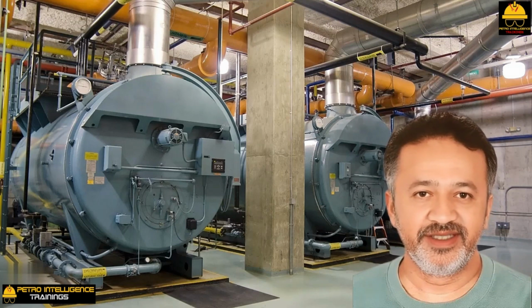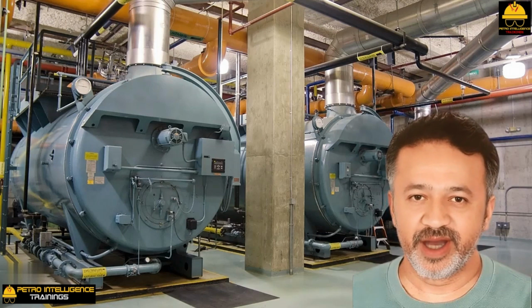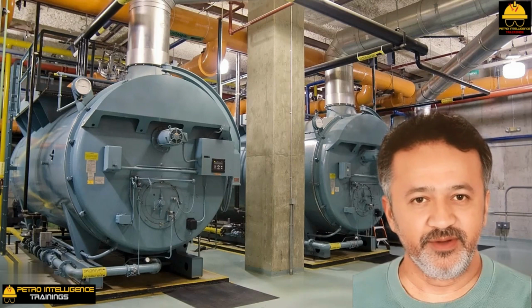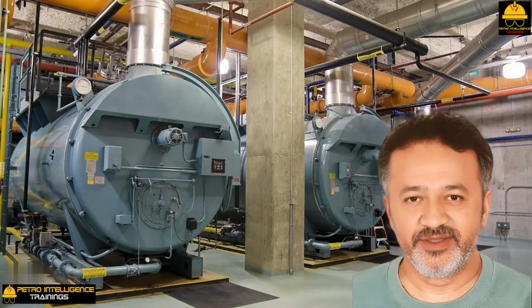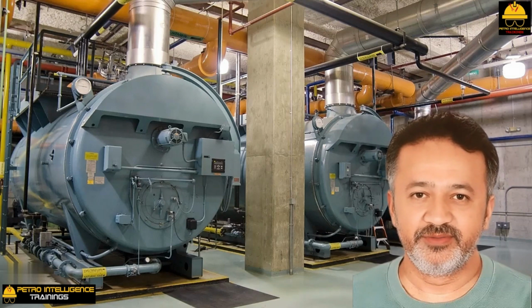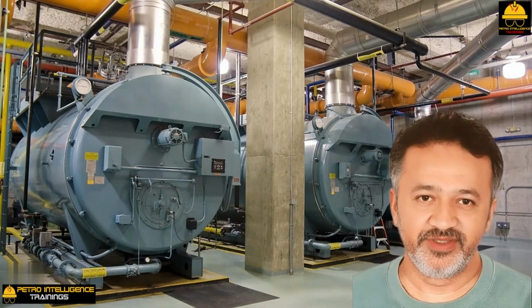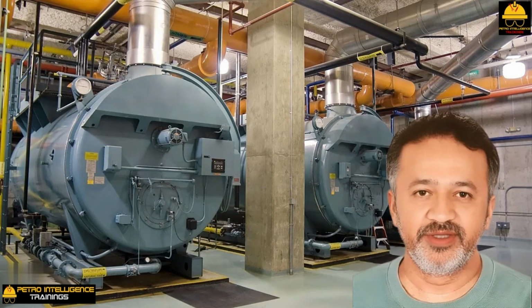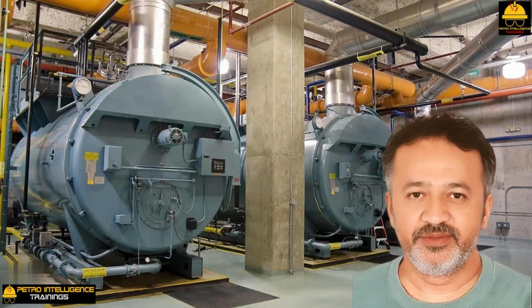Depositing on turbine blades. The deposits eventually get so thick that they break off and unbalance the rotor. Resulting vibrations then cause the turbine to trip off, and stress corrosion of the blades causes sudden failure. Fouling of vacuum system ejector steam nozzles. The TDS content of BFW should be minimized by upstream treating. In former days, hot lime water softening was employed. In most modern process units, ion exchange resin is used to demineralize BFW.